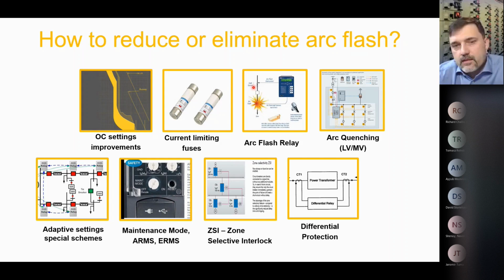I would say the next solution might be the Arc Flash relay. By Arc Flash relay I mean a relay that looks like a protection relay and has a detection system, so fiber optic sensors, pressure sensors, light sensors. It will detect the arc and also has voltage or current criteria to distinguish what kind of fault we have. This system might also be expanded to arc quenching. It might be on medium voltage and low voltage systems, but arc quenching is an expansion of the system with a quencher, which is a switching off device that actively switches off the arc flash. I will show you an example later in more detail.